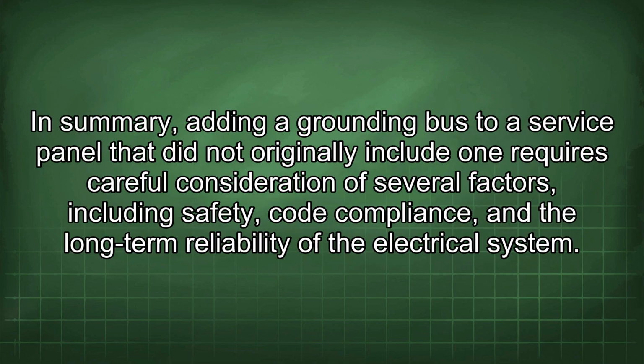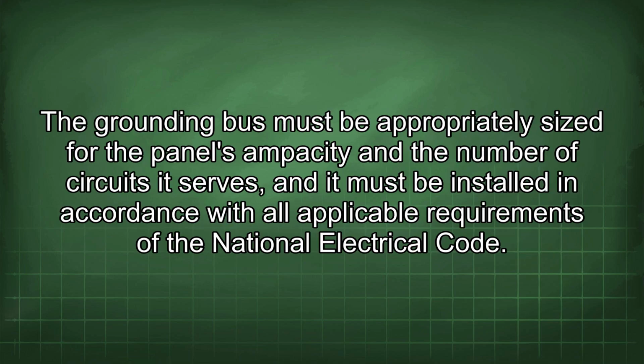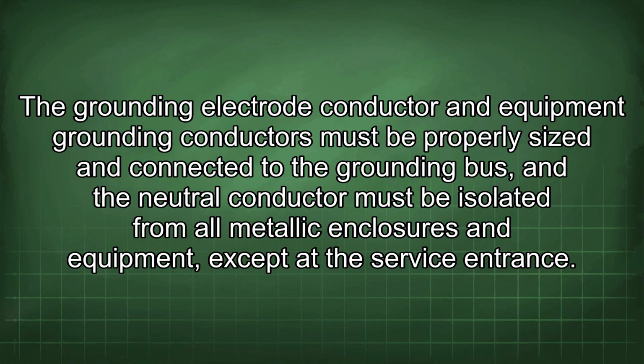In summary, adding a grounding bus to a service panel that did not originally include one requires careful consideration of several factors, including safety, code compliance, and the long-term reliability of the electrical system. The grounding bus must be appropriately sized for the panel's capacity and the number of circuits it serves, and it must be installed in accordance with all applicable requirements of the National Electrical Code. The grounding electrode conductor and equipment grounding conductors must be properly sized and connected to the grounding bus, and the neutral conductor must be isolated from all metallic enclosures and equipment except at the service entrance.